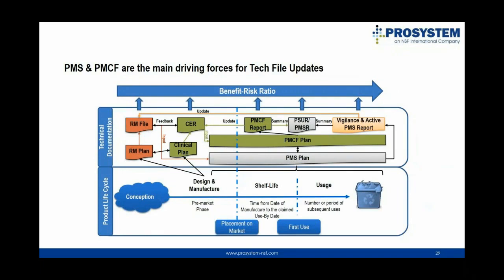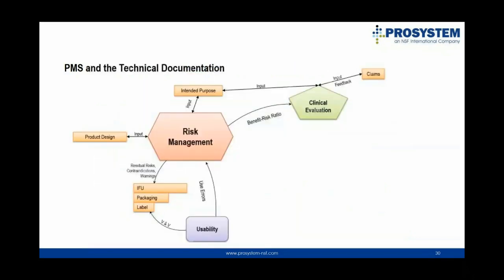When talking about the design phases of a medical device, creating the PMS and PMCF plans makes most sense at the end of the design period, once a possible lack of clinical data has been identified, or critical residual risks after completing risk management activities remain, and which require further monitoring. So the plans for risk management, clinical evaluation, PMS and PMCF are part of the technical documentation, and you can see the interdependencies between the plans and the reports, which contribute eventually to the benefit risk determination. At the design stage, the risk management and clinical plans are the main driving forces for creating the required objective evidences of the technical documentation.